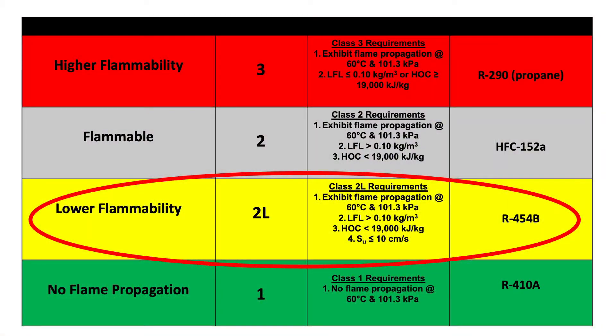Going back to the ASHRAE Standard 34 definition, we're really focusing on the A2L class — the lower flammability refrigerants. They're not non-flammable class one, but they're not class three either, where we have the hydrocarbons like butane and propane — the highly flammable refrigerants. It used to be called mildly flammable, but we're moving away from that language. Lower flammability refrigerants is where we want to focus.